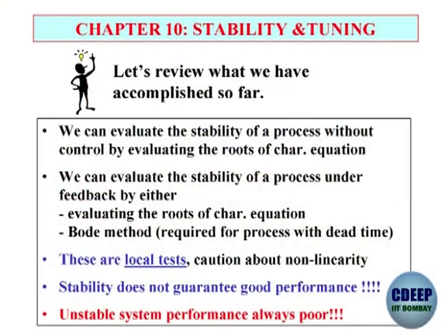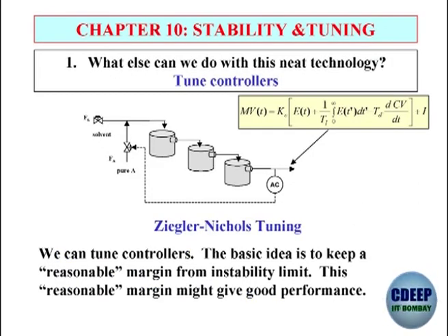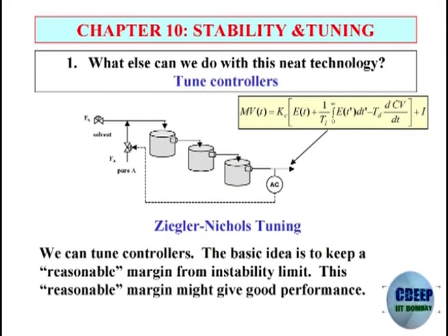The whole problem comes because almost always we have processes with dead time. You cannot go for the roots of characteristic equation approach — you have to go for some other criterion like the Bode stability criterion or the Nichols criterion. The Routh-Hurwitz criterion cannot be used now for systems with time delay. Stability does not guarantee good performance. The first consideration is to make sure the loop is stable. The basic idea of tuning controllers is to keep a reasonable margin from instability. That is why in the Ziegler-Nichols tuning formula, you find the K_c required for marginally stable system and then divide it by half — 50 percent reduction — to keep a good margin from instability.